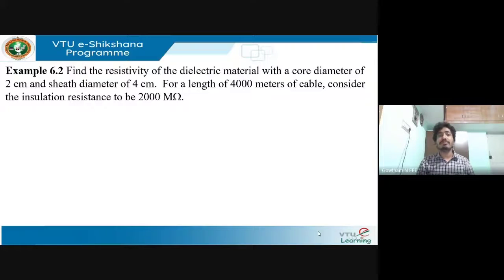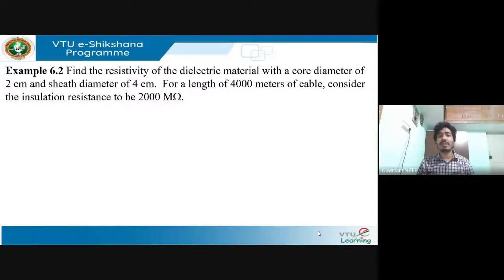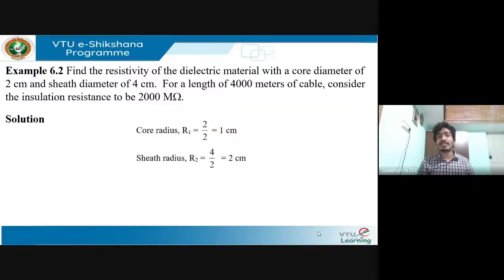The next problem asks us to find the resistivity of the dielectric material. The core diameter is 2 cm and sheath diameter is 4 cm, for a cable length of 4000 meters with insulation resistance of 2000 mega-ohms. Core radius r1 = 2/2 = 1 cm, sheath radius r2 = 4/2 = 2 cm. The value of ln(r2/r1) = ln(2/1) = 0.6931.